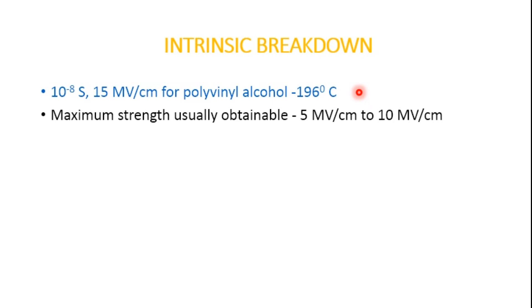Coming to the first type — intrinsic breakdown. When voltage is applied for a short duration of the order of 10⁻⁸ seconds, the dielectric strength of the solid material increases relatively rapidly up to an upper limit called the intrinsic electric strength. The maximum electrical strength recorded is 15 MV per centimeter for polyvinyl alcohol at -196°C. Usually the maximum strength is up to 10 MV per centimeter under experimental conditions.